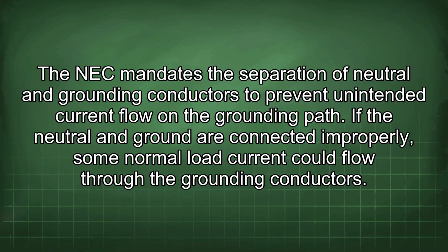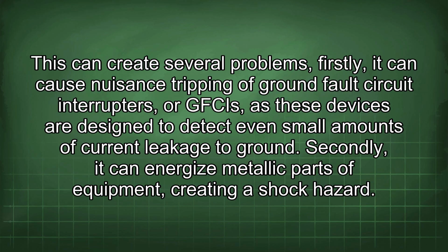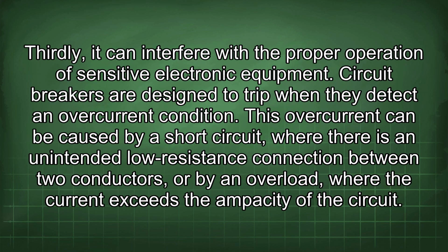The NEC mandates the separation of neutral and grounding conductors to prevent unintended current flow on the grounding path. If the neutral and ground are connected improperly, some normal load current could flow through the grounding conductors. This can create several problems. Firstly, it can cause nuisance tripping of ground fault circuit interrupters, or GFCIs, as these devices are designed to detect even small amounts of current leakage to ground. Secondly, it can energize metallic parts of equipment, creating a shock hazard. Thirdly, it can interfere with the proper operation of sensitive electronic equipment.